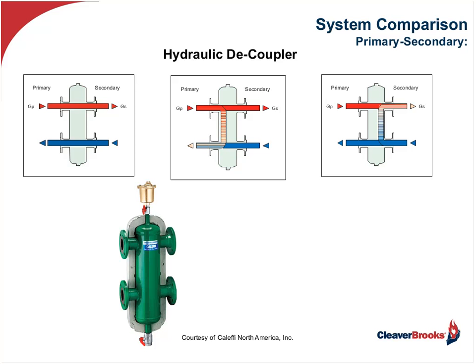If the secondary flow or the system flow is higher than the primary flow, you will get flow coming back around, or cold return water coming back around, decreasing your supply water temperature out to the system. That's generally not a good thing in most circumstances, because it's going to decrease your heat output. Now, in the last couple of years, several manufacturers have taken the idea of a straight piece of pipe and come out with dedicated decoupling devices. Sometimes they include buffer tanks or air vents, as you see here. But whether it's a straight piece of pipe or a true hydraulic decoupler, you have to understand how it works and the impact it has on the system.